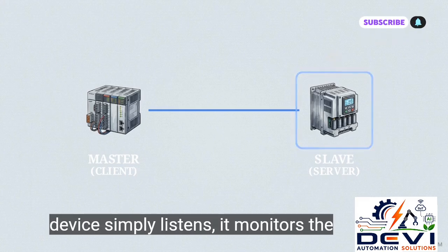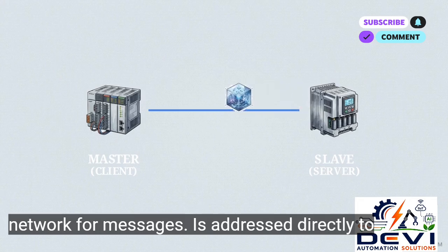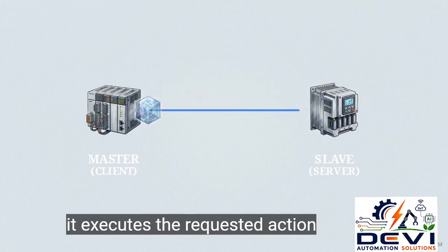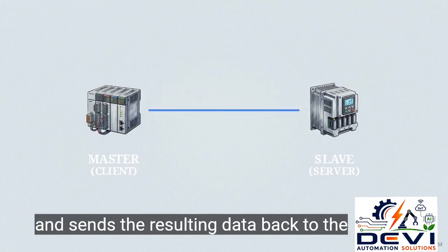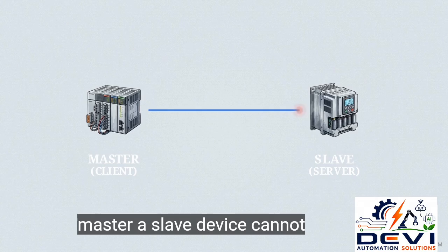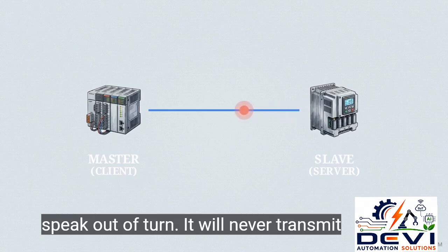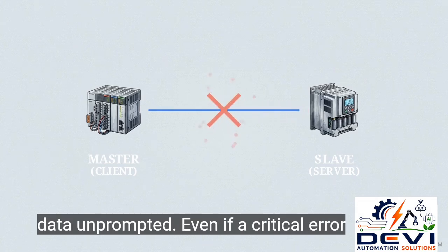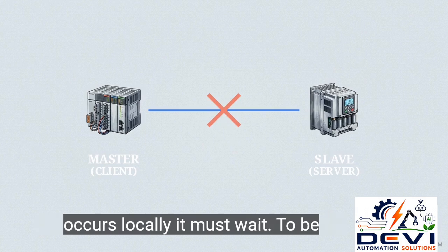The slave device simply listens. It monitors the network for messages addressed directly to it, executes the requested action, and sends the resulting data back to the master. A slave device cannot speak out of turn. It will never transmit data unprompted, even if a critical error occurs locally. It must wait to be asked.